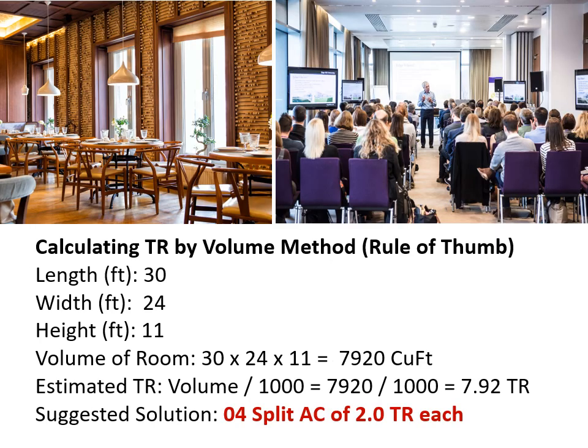Another example: for a restaurant, seminar room, conference room, or classroom with dimensions 30 ft × 24 ft × 11 ft, the total volume is 7920 cubic feet. Dividing by 1000 gives 7.92 TR. So we can safely say that 4 split ACs of 2 tonnes each shall be required for this space.